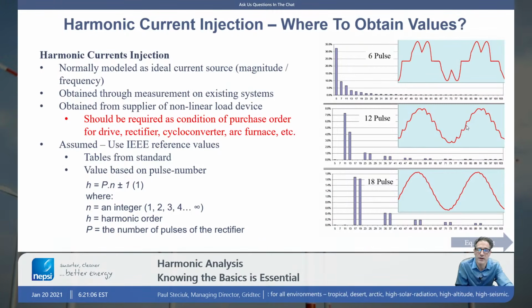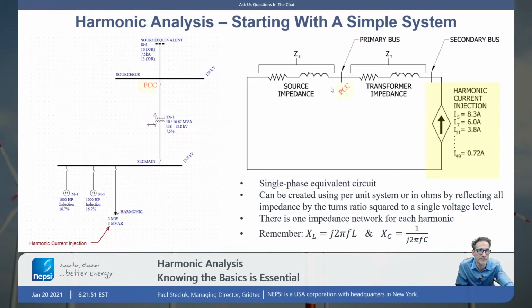note that depending upon a nonlinear load, there are characteristic harmonics for various devices. You might have what's called 6-pulse, 12-pulse, 18-pulse devices, and they have characteristic harmonics that you can evaluate for your load. I don't really have time to get into all the details here, but just know that if it's a rectifier, if it's a cycloconverter, if it's a VFD drive that's got a certain pulse number, there is a characteristic signature of that device. In other words, what harmonic currents it's going to inject in the network. So it's worth noting that you don't necessarily need to have data from the supplier to do harmonic analysis. You can make some assumptions. And if you make those assumptions conservative, you're probably okay.